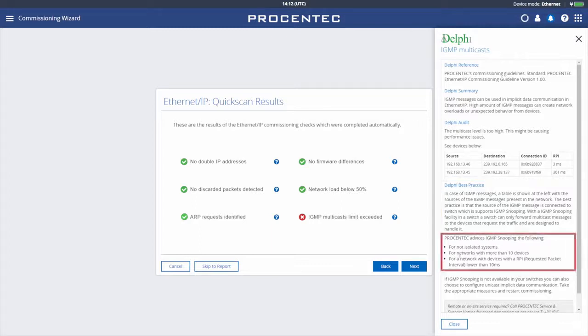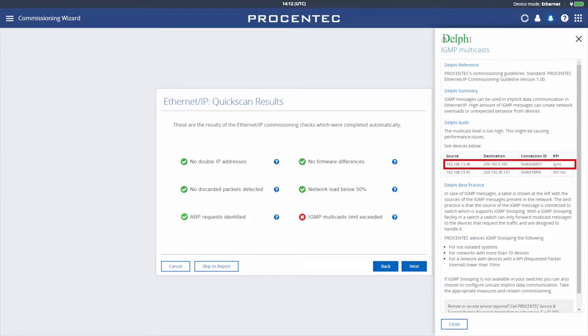It states snooping is helpful for a network with devices with an RPI lower than 10 milliseconds. Above you see that this is the case on your network with a measurement of 3 milliseconds. If snooping was active, you would not see the multicasting.